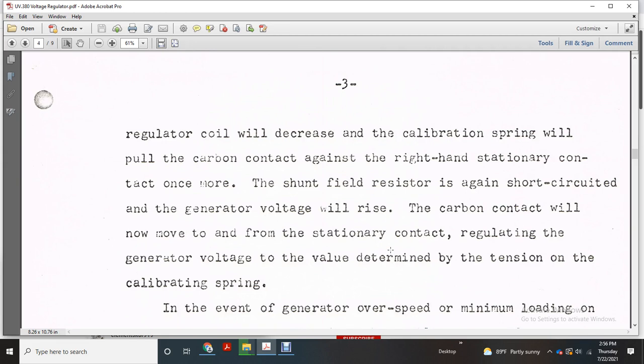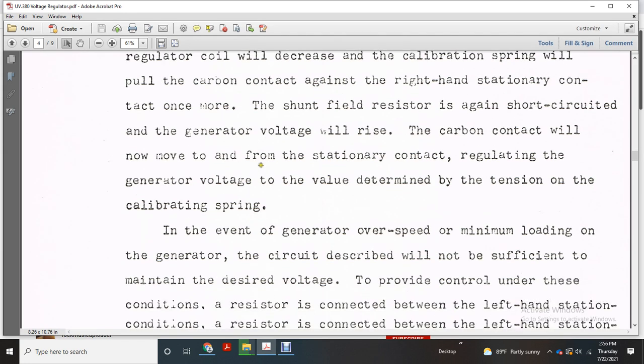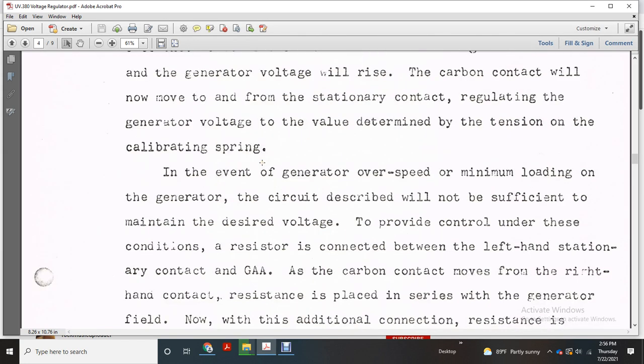Alright, the regulator coil magnetic strength will decrease, the calibrating spring will pull the carbon contact against the right hand stationary contact once more, the shunt resistor will again be short circuited, and the generator voltage will rise. The carbon contact will move to and from the stationary contact, regulating the generator voltage to the value determined by the tension of the calibration spring. In the event of generator overspeed with minimum loading, the circuit described will not be sufficient to maintain the desired voltage, so the regulator provides for control under these conditions.